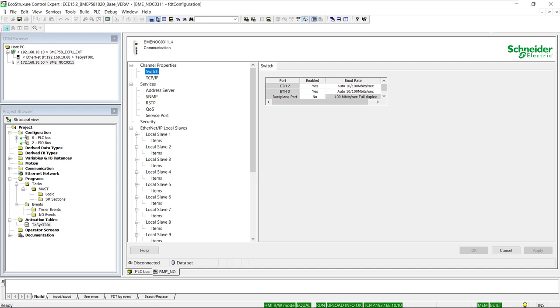In this scenario, since the NOC0311 module is isolated from the Ethernet network of the CPU, it will not be possible to remotely view the embedded web page of the CPU or connect online to its DTM to find the MAC address or firmware version. However, using explicit communication function blocks within the PLC logic, we will be able to access this information and make it available as PLC registers accessible by the SCADA system.